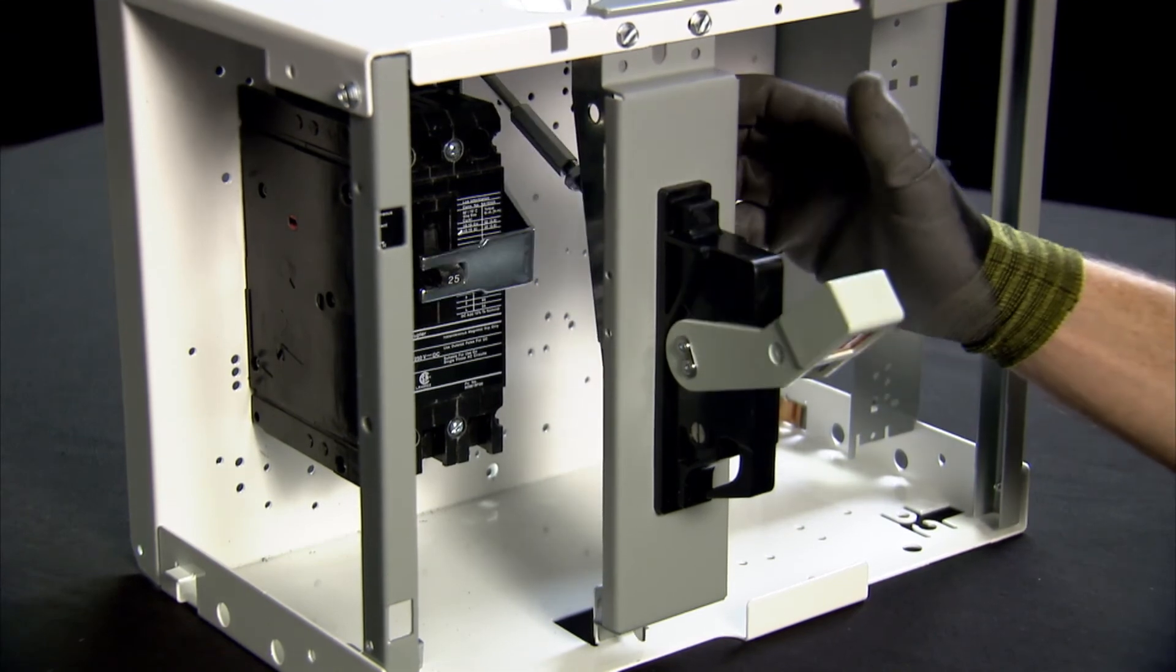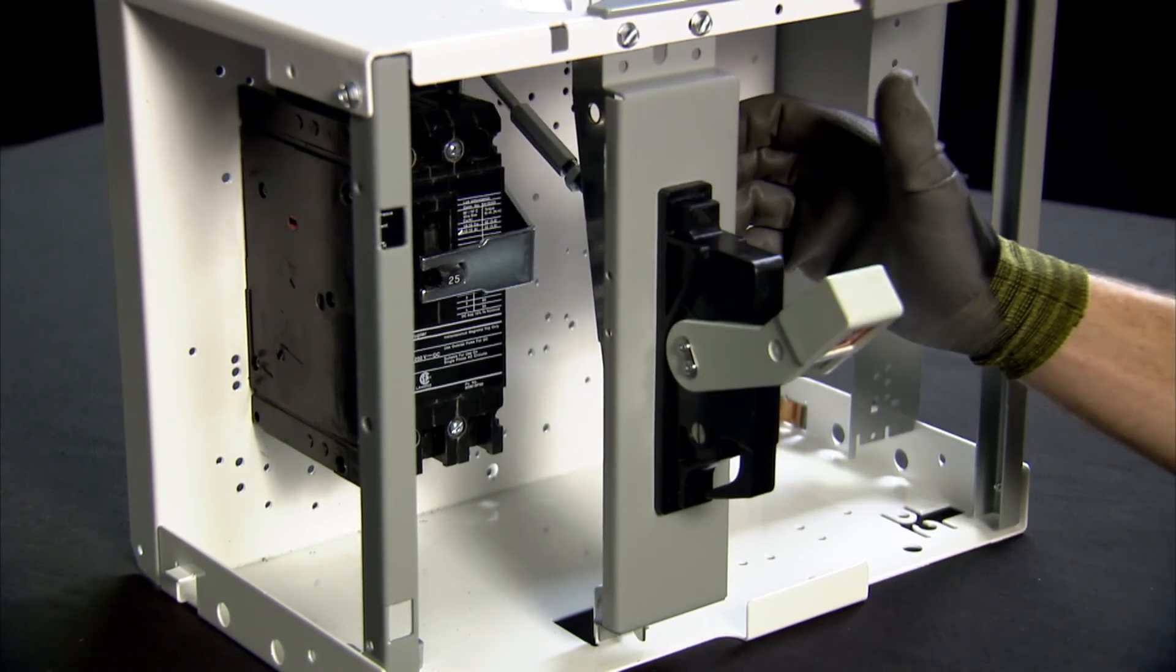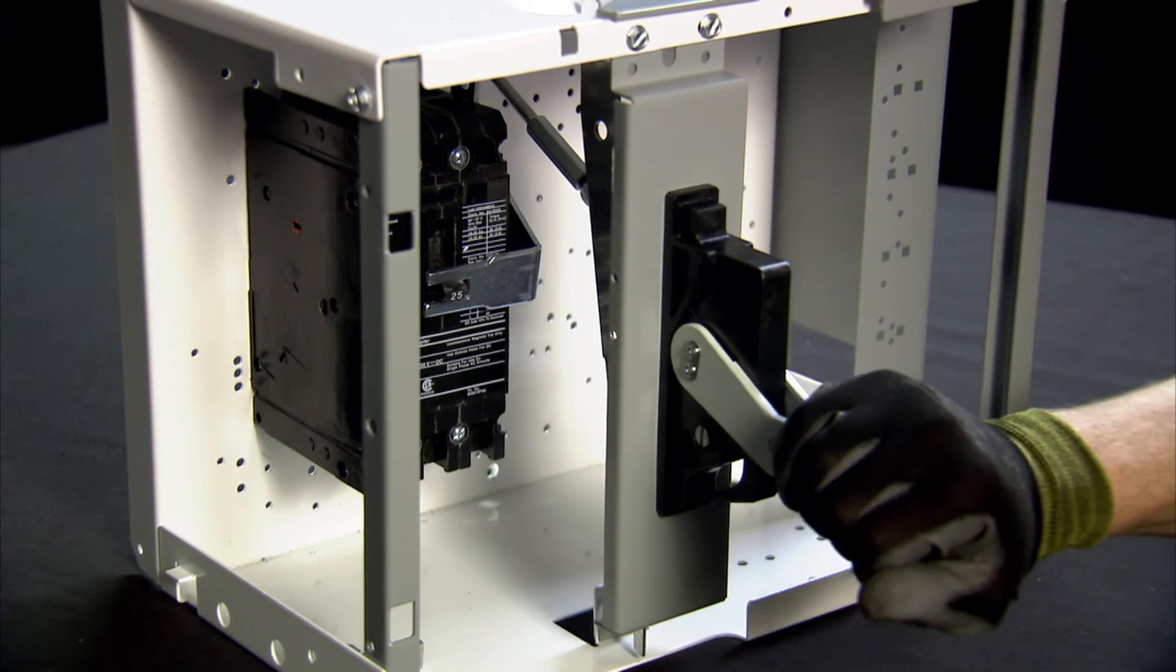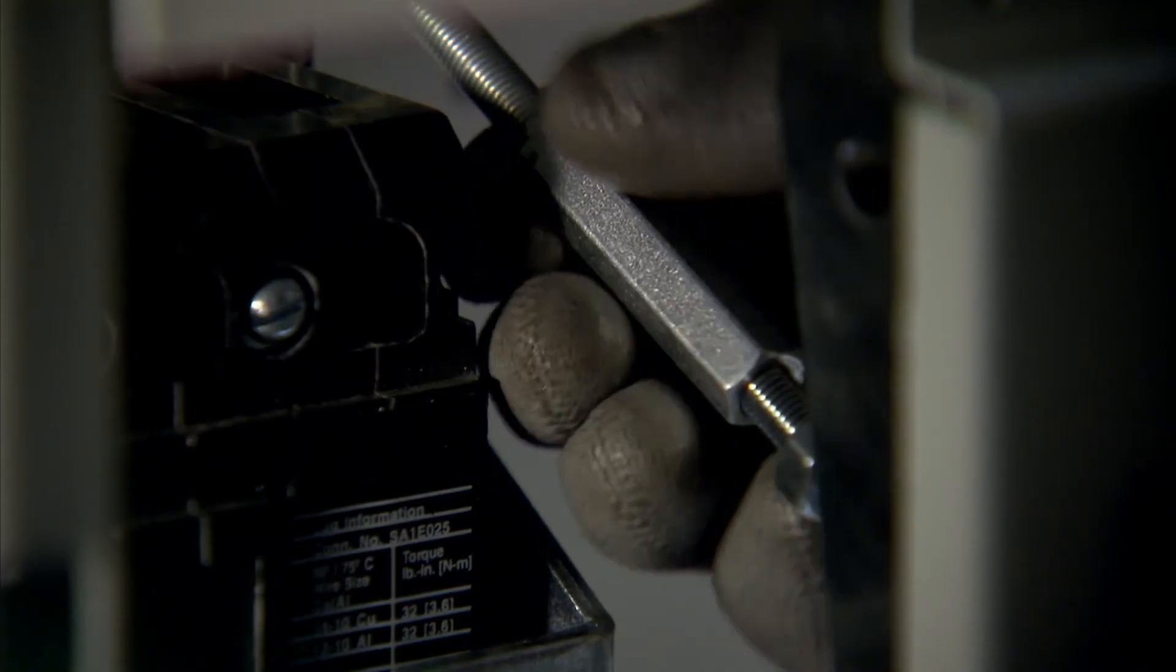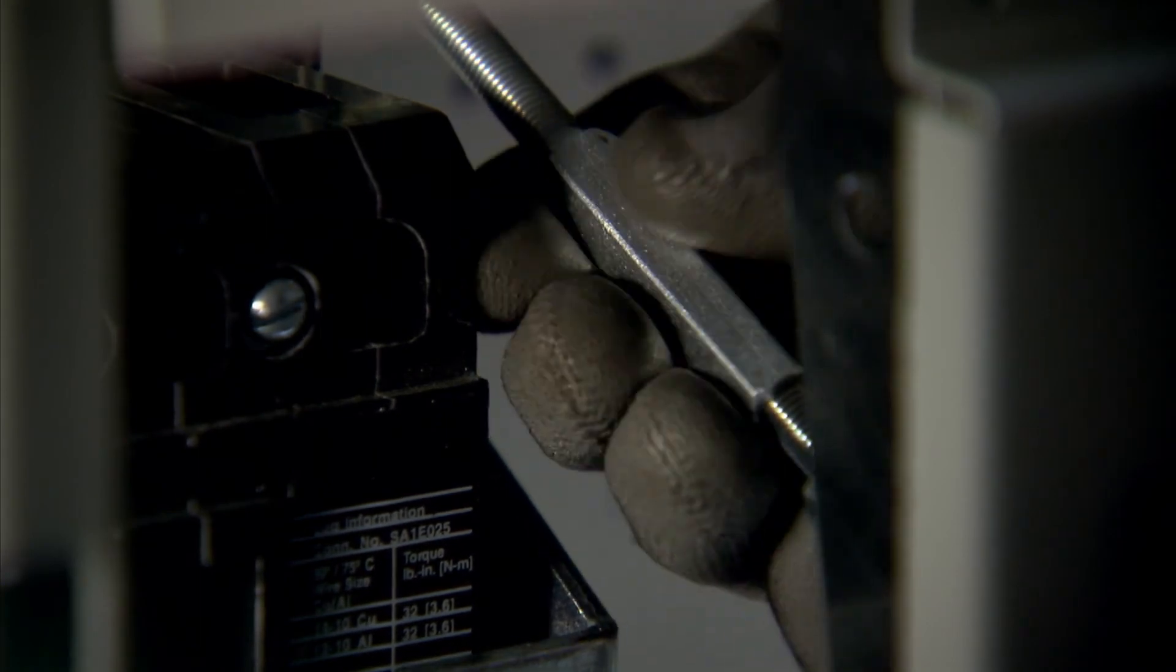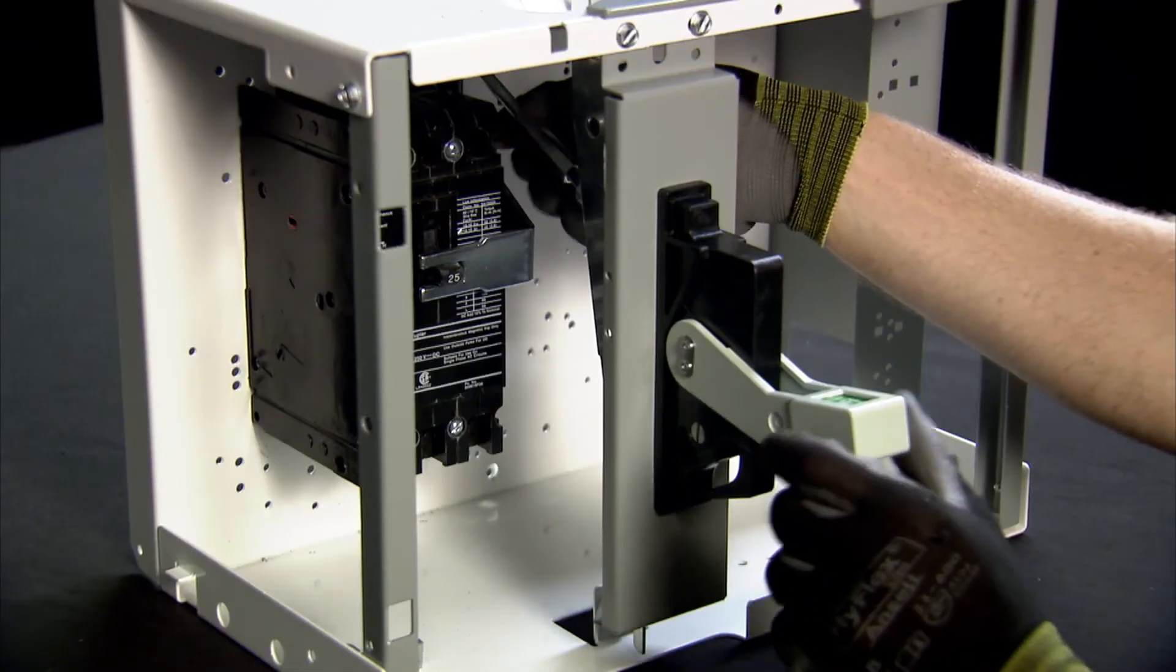If the handle will not switch the breaker to the on position and will not move fully into the off position, the length of the connecting rod is too short and must be lengthened. Rotate the turnbuckle clockwise to lengthen the rod until the switch is properly adjusted.